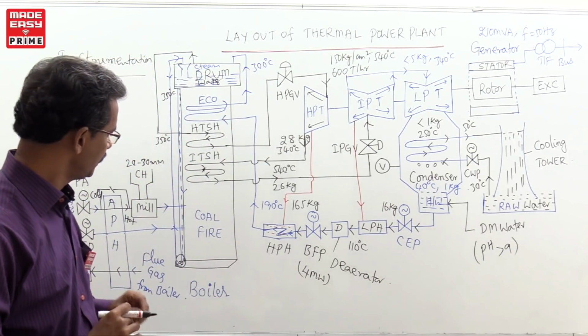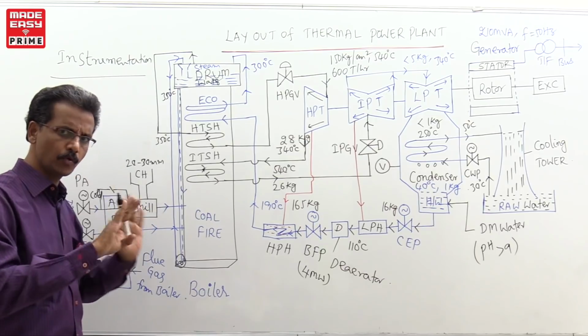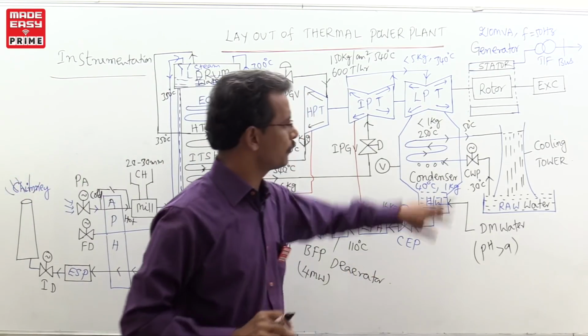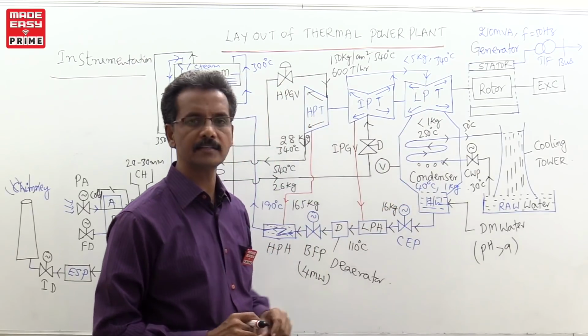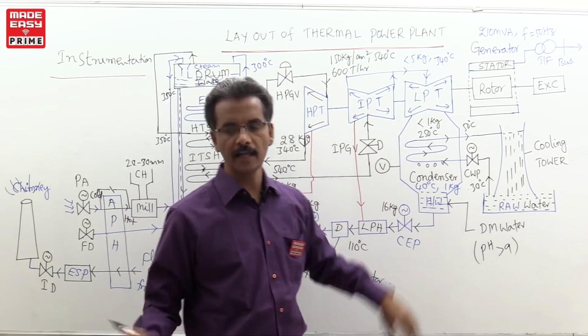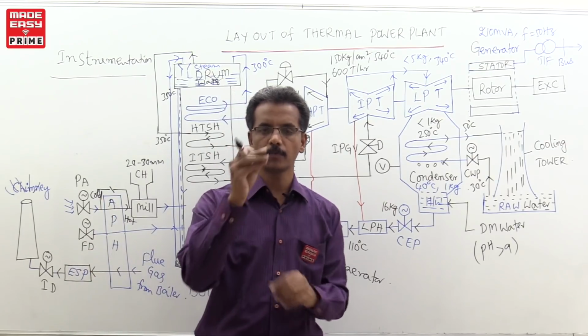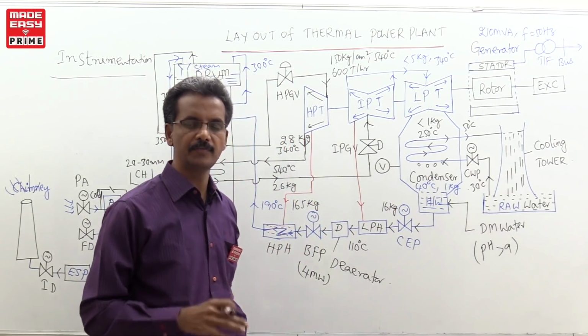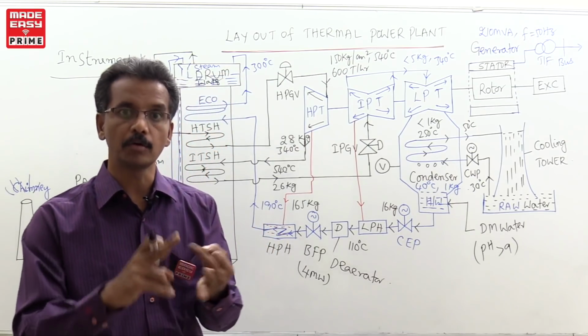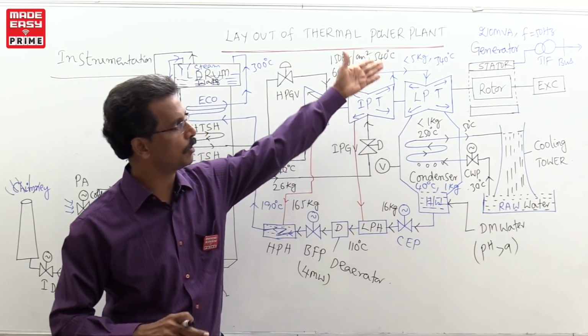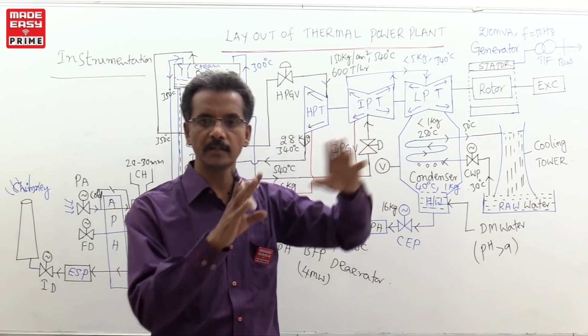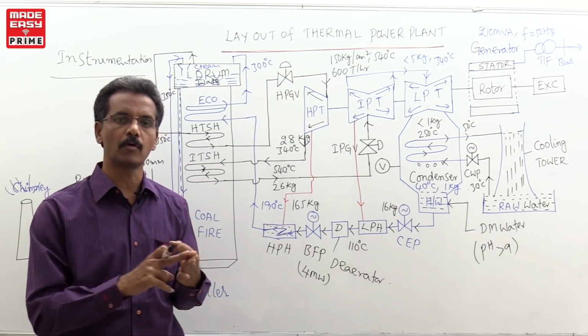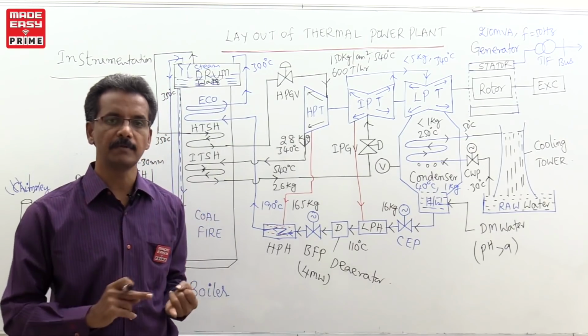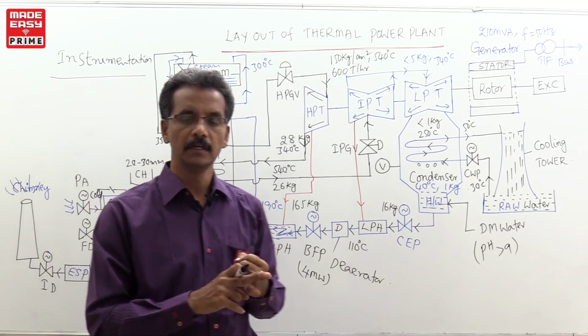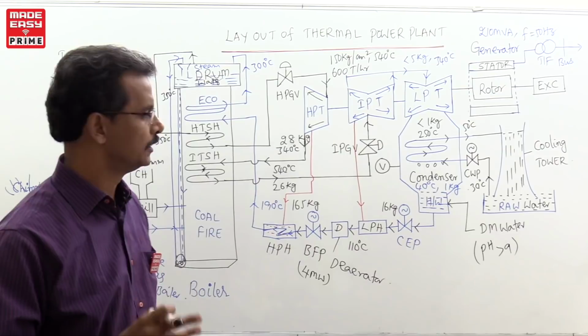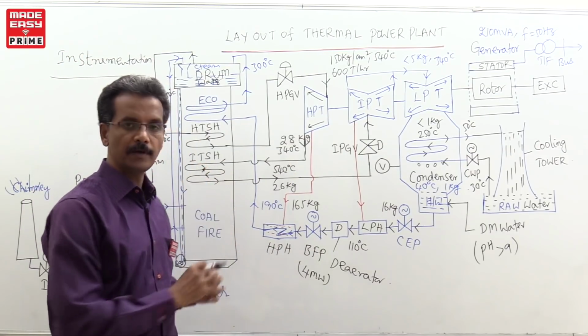And one more thing, here you can think of, everywhere some flow rate, pressure, and temperatures are there. And one more point, once the equipment like the condensate extraction pump or BFP motors, as well as these fans and everything is there, for that you have to provide proper voltage, proper current, proper frequency. How to measure the current, how to measure the voltage, how to measure the frequency, how to measure the power and energy from the output of the generators. Clear? For this we have to think of all the instruments like voltmeter, ammeter, wattmeter, energy meter, power factor meter, frequency meter and some of the instrument transformers. These things also play a major role and are important for the main instrumentation students.